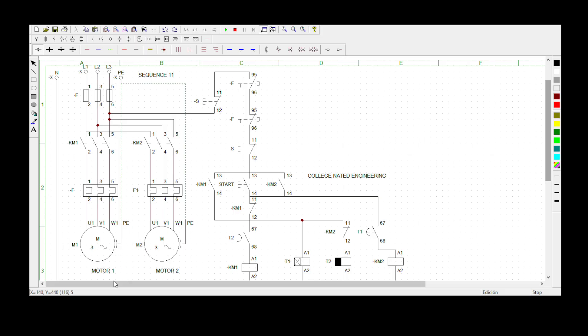To summarize the statement: when the start button is activated, Motor 1 must start rotating. Only after 10 seconds can Motor 2 be started by activating the same start button while Motor 1 keeps rotating. Then 10 seconds after Motor 2 has started rotating, Motor 1 must stop automatically and Motor 2 must keep on rotating. Now let's look at the control circuit.